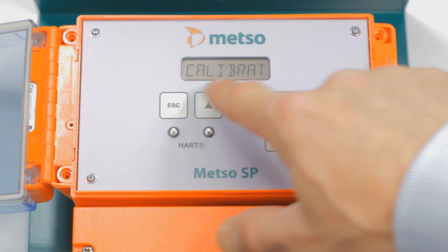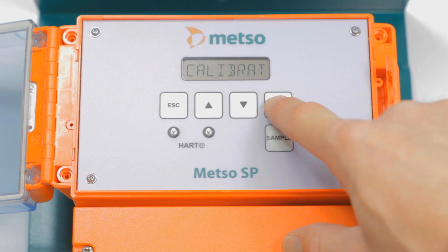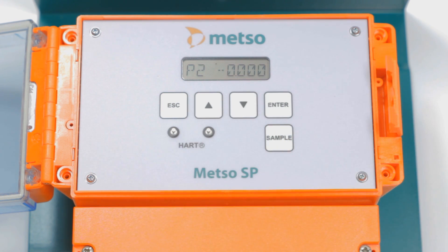Now, when we get our results from the lab, we're going to go back into the calibration menu, hit new recipe, one, softwood unbleached, ash, P1, P2. Now, the lab came back and said the consistency was 3.00%. That is a reading of 0.26 higher than the lab.